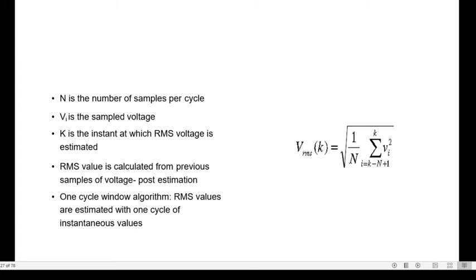So the next characteristic is the sag duration. That will define the duration for which the sag persists in the system. So voltage sag duration is the duration in which the voltage is dropped. The duration of the sag is equal to the fault clearing time, or the number of cycles during which the RMS voltage is below a given threshold value. Basically one can have different types of sag: instantaneous, momentary and temporary. Instantaneous sags are between 0.5 and 30 cycles, momentary 30 cycles to 3 seconds, and temporary 3 seconds to 1 minute.